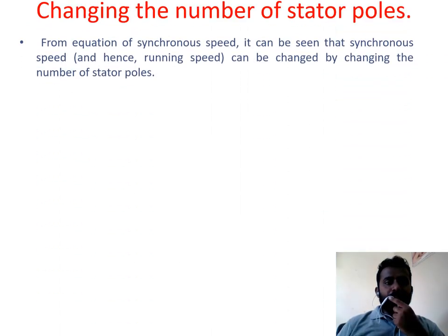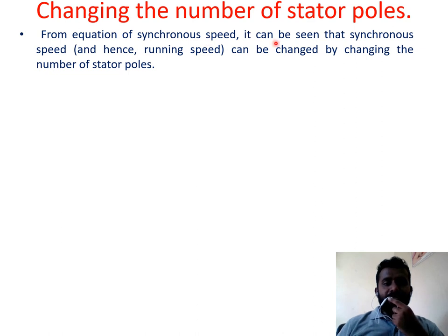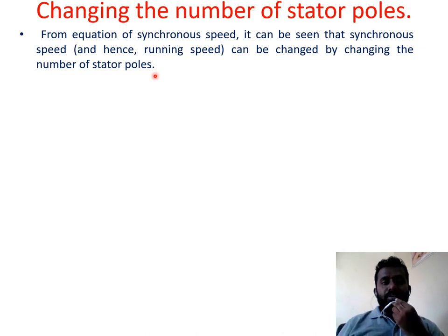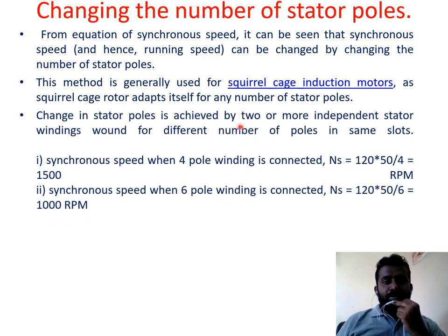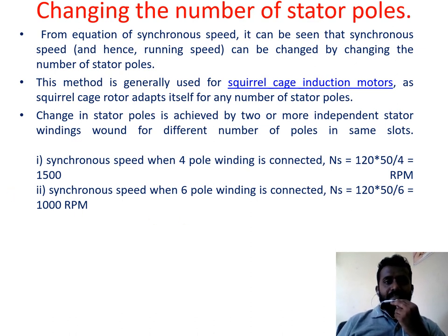Changing the number of stator poles: from the synchronous speed equation NS = 120F/P, it can be seen that synchronous speed can be changed by changing the number of stator poles P. This method is generally used for squirrel cage induction motors as the squirrel cage rotor adapts itself for any number of stator poles. Change in stator poles is achieved by two or more independent stator windings. For example, if poles = 4, speed = 1500 RPM; if poles = 6, speed = 1000 RPM.